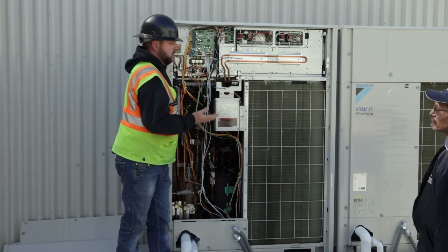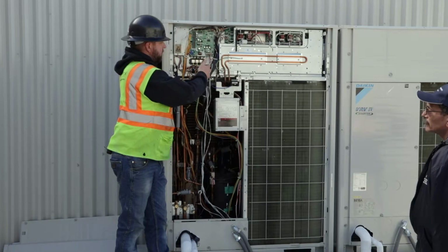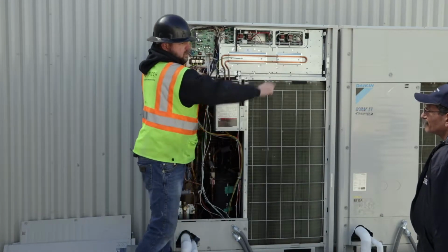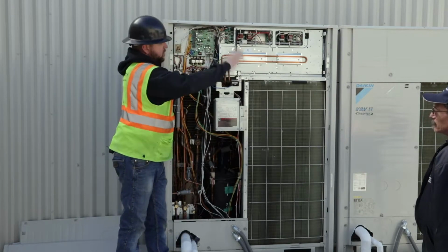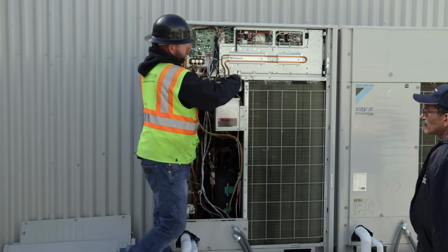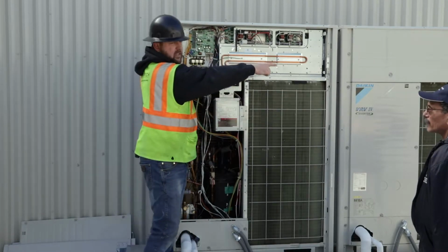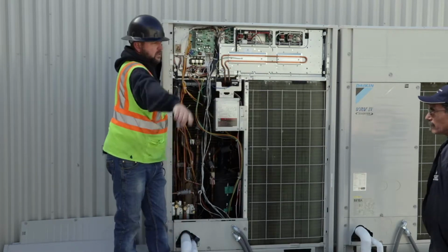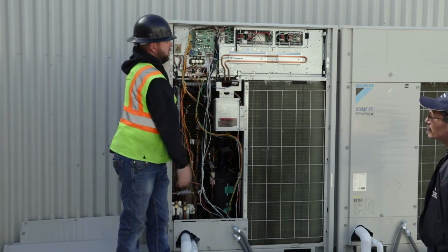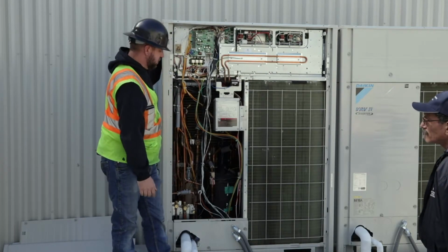Another way to do it is take this wire off, bring it over there, and make that your master. What you do is kill power to your master and your slave at the same time. Move your wire over, and only turn power on to your slave. Now it's going to think that that's the master, and it'll reinitialize through all your fan coils, and that'll become your master until you get this one repaired as well.